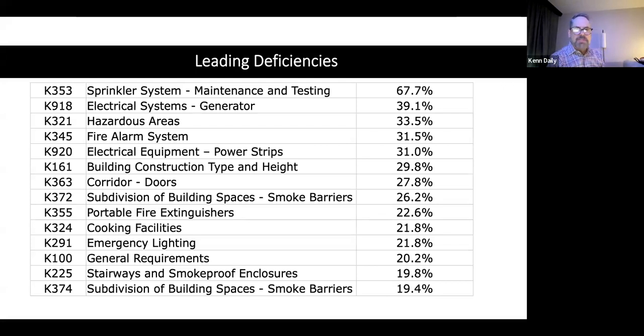K372, subdivision of spaces, smoke barriers. This is where you have penetrations. Surveyors are finding penetrations, holes in subdivisions. So you go up in your attic or the space above your general area, your building, and you find where the smoke barriers have had holes run through them by HVAC or plumbing or IT individuals, and they're not sealed appropriately. And you have portable fire extinguishers, and then cooking facilities, emergency lighting at exits.